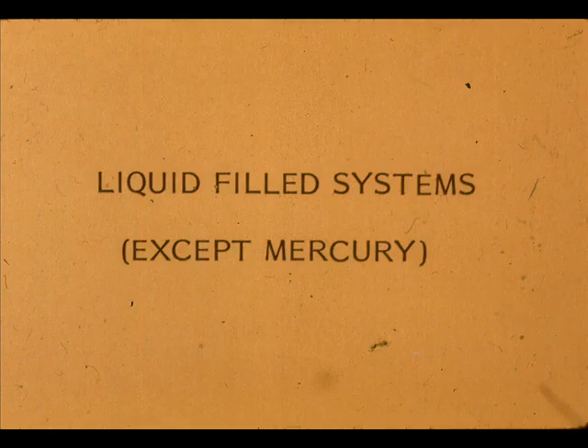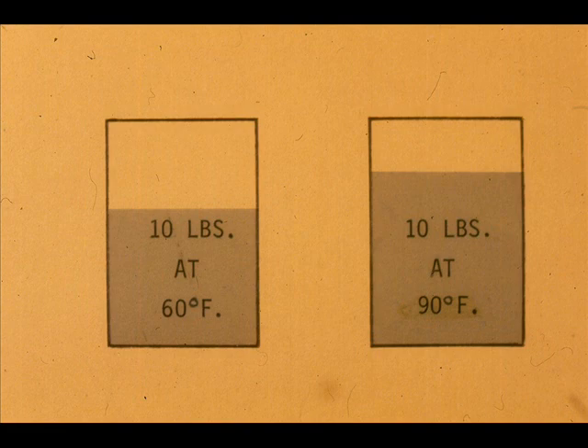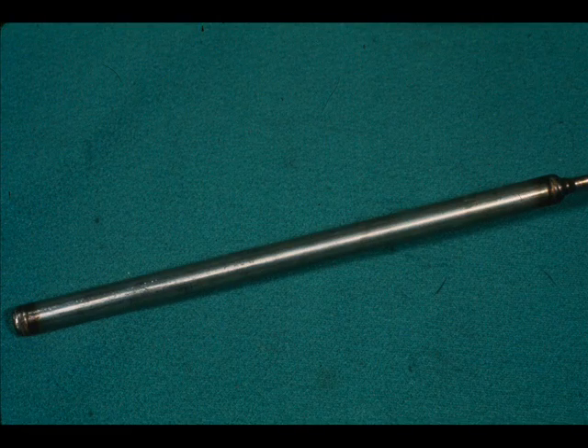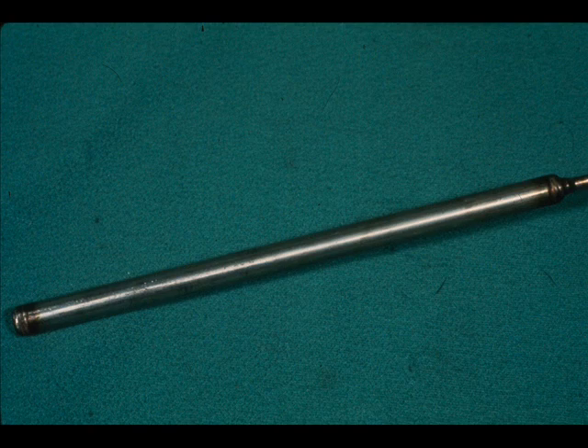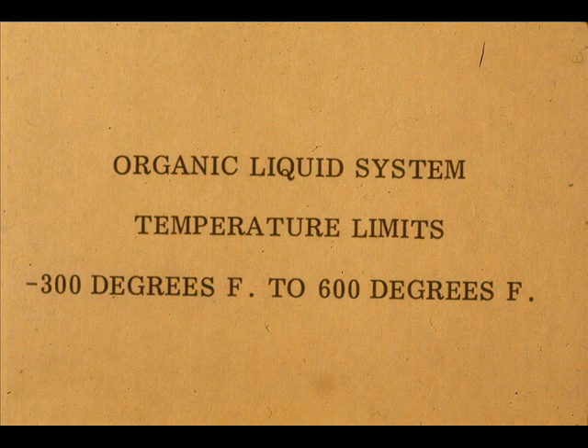We will first study the liquid fill systems. Liquid systems operate on the principle of volume expansion of the filling liquid with an increase in temperature. The loading pressure induced in the fill system is incidental. Xylene or other organic liquid may be used as the filler. The organic liquids have a lower freezing point than mercury and are used for low temperature applications. The temperature limits for the organic liquid system are minus 300 degrees Fahrenheit to 600 degrees Fahrenheit.